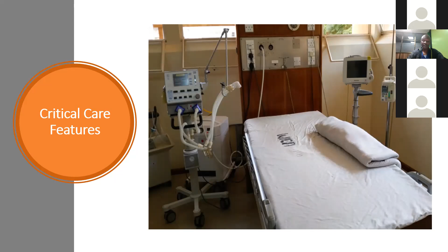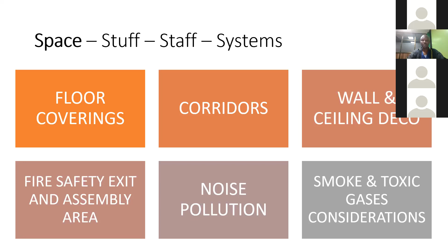Generally, the size and type of therapies are influenced by the volume effect correlation. Building hygiene should involve proper management of clean and dirty water, control of temperature, humidity, light, and ventilation, which can be balanced between natural and artificial. Microclimates affect well-being of care providers and patient outcomes. Material used for walls, floor, and roof should be impervious and sound absorptive. Considerations for smoke and toxic gases, which involves containment, that is use of resistant material, or disposal, or pressurization for prevention of smoke entry, must be implemented when building the ICU.